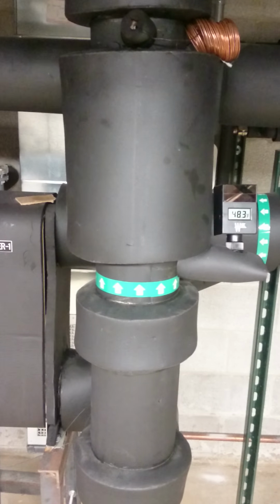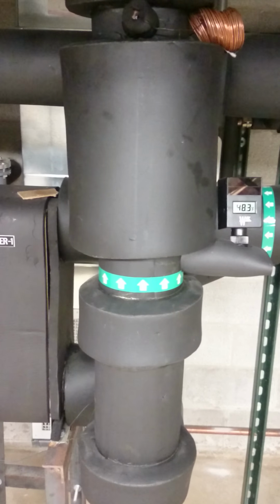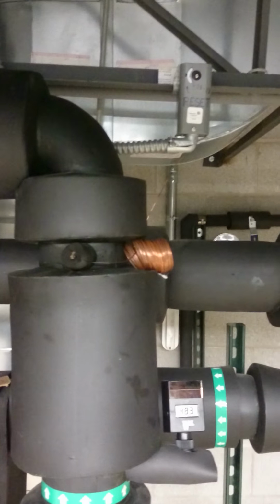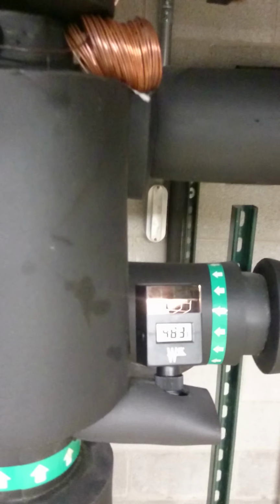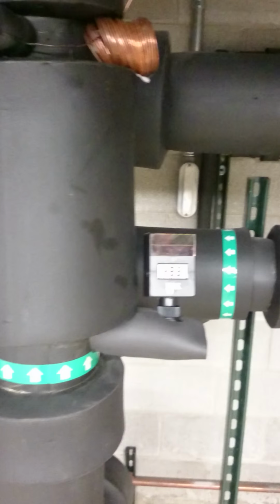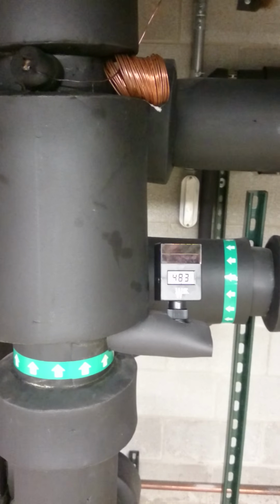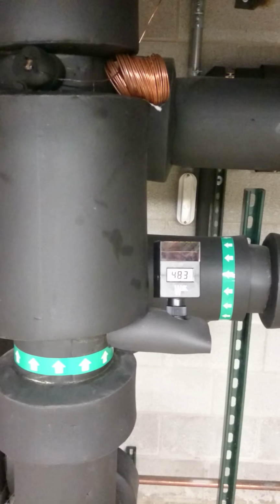It wasn't until I was finally out here on a cool day that I found that I was running with an outlet water temp, pretty consistent, 40, 41 degrees. Suddenly, it started dropping off. So I had to determine why on a mild day would I go from 40 degrees down to our Freezestat trip of about 35 degrees. And that happened quicker than that stage controller was able to stage this unit down.